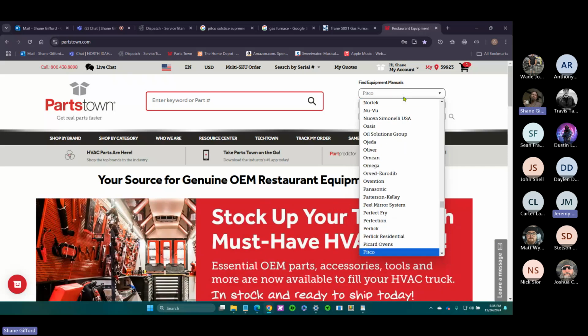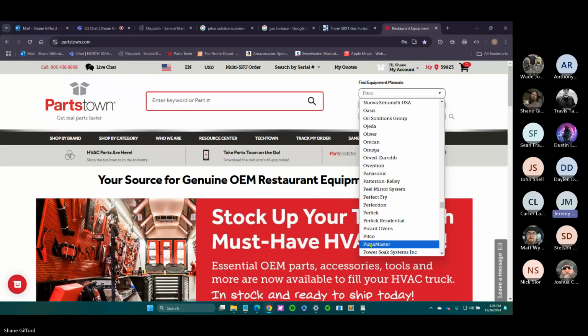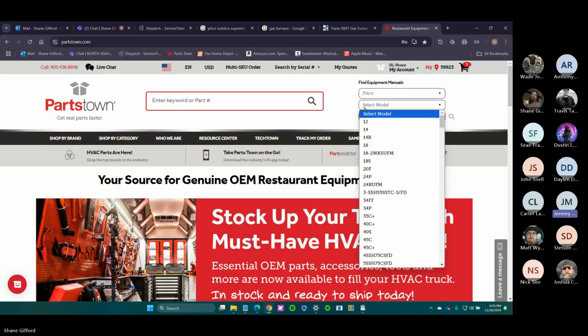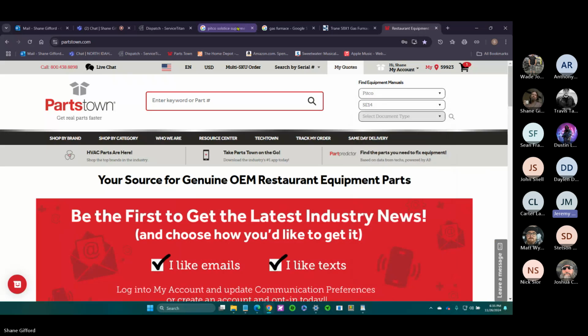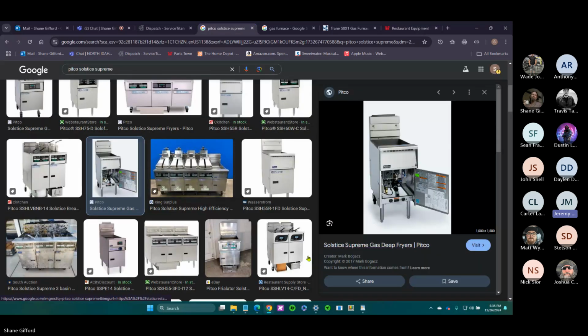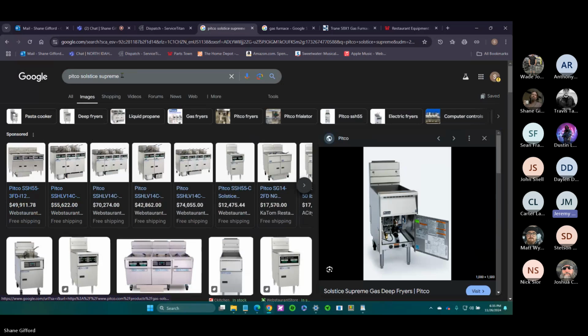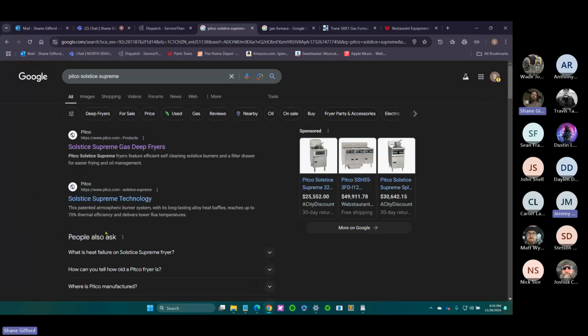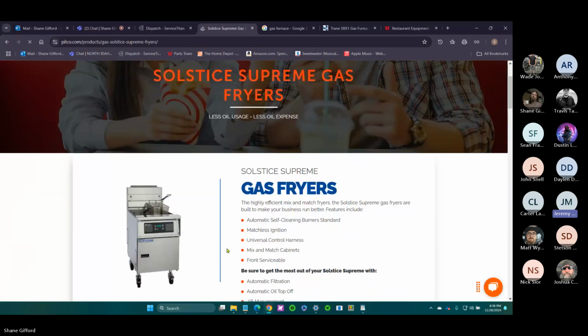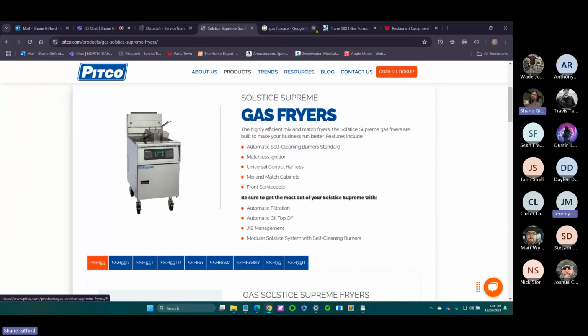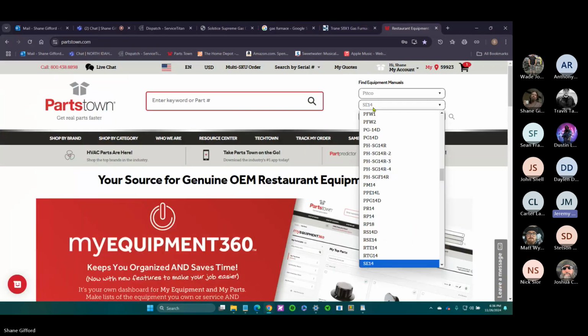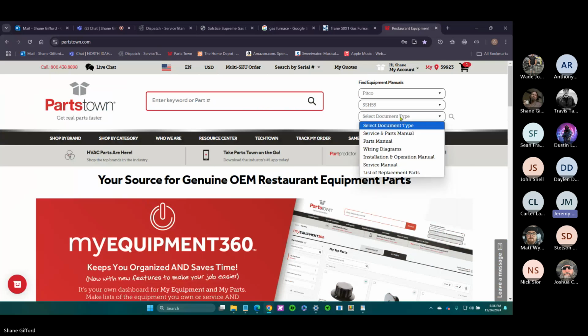Ohming out those temperature sensors is huge, because they're only off by maybe like 1,000 ohms, and it'll be off by a good 150 to 200 degrees. I have one at Five Guys on order right now. That one was tripping the high limit, and at the high limit at 400, it's only supposed to be sub 500 ohms, and it was at like 2,500, which was registering like 270 degrees. So those temperature probes definitely go bad more often than they don't, or that seems to be my biggest call to the Five Guys fryers anyway.